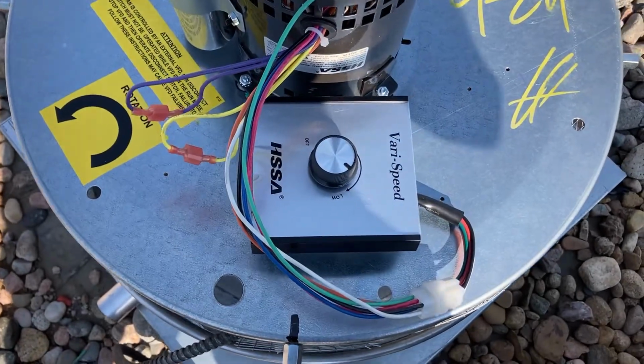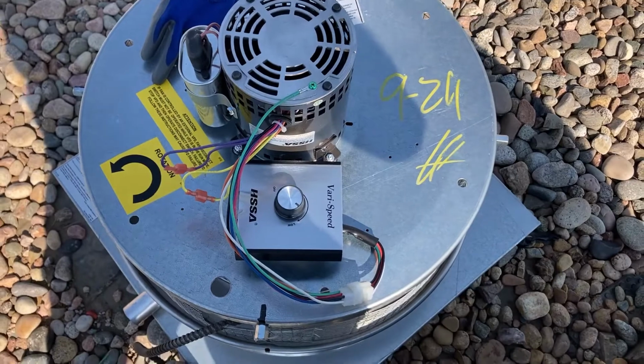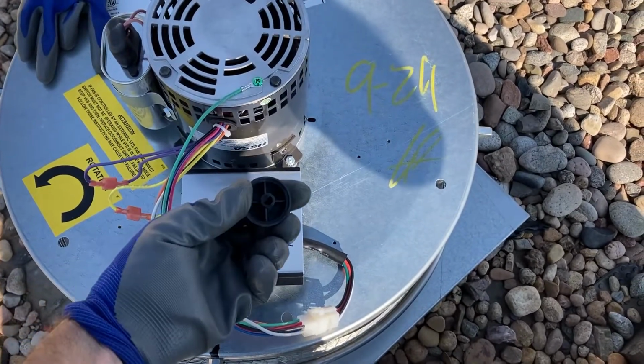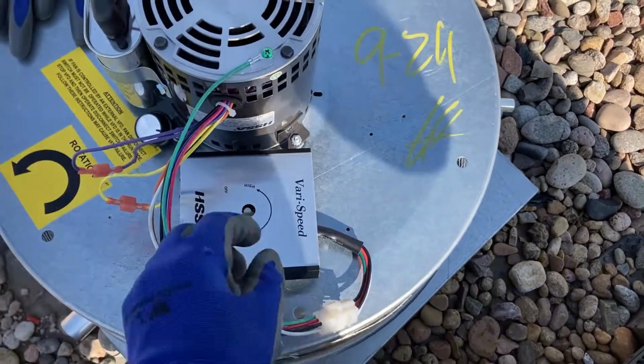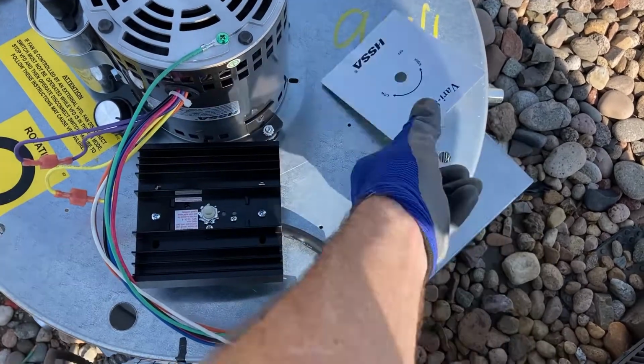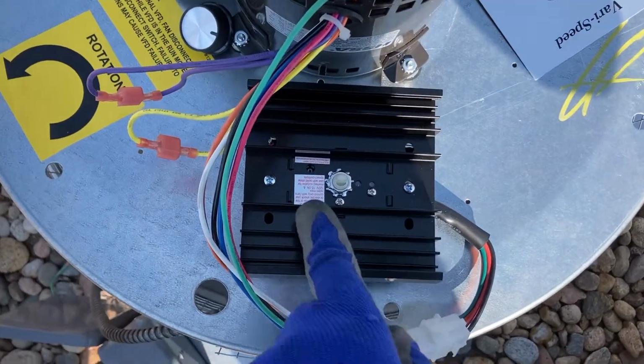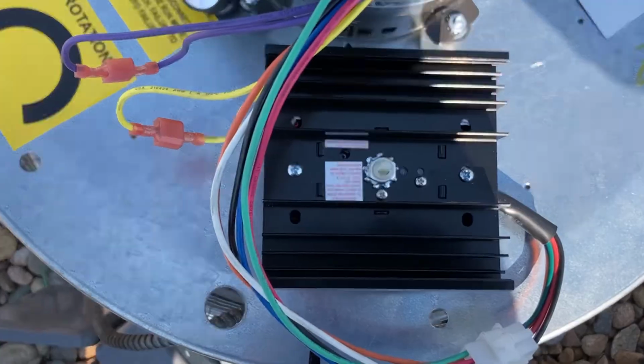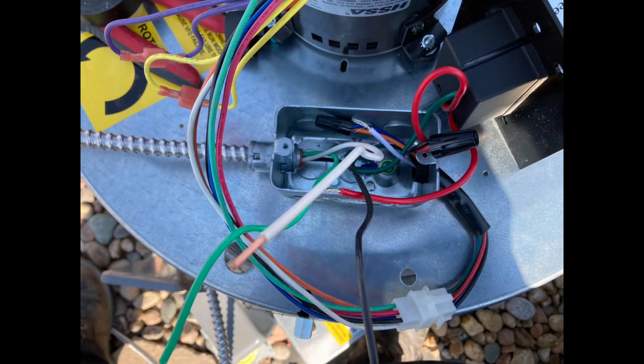Now let's move on to the electrical. It comes with this variable speed drive control right here. So you simply pull the knob off, slide this aluminum cover off. There's a heat sink. You undo those two screws and it exposes the J-box and your wire connections. So you make up your wire connections. Again, this is 120 volt single phase.